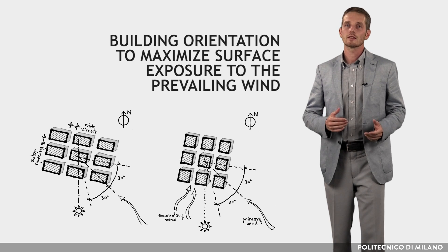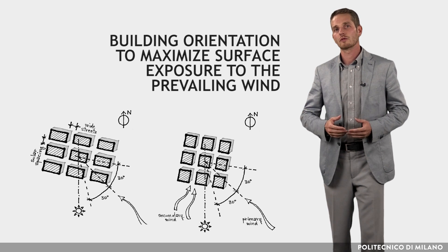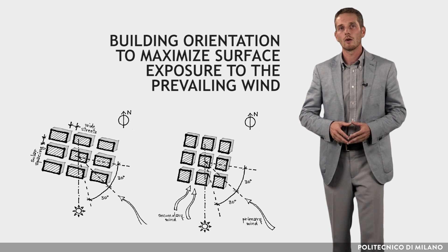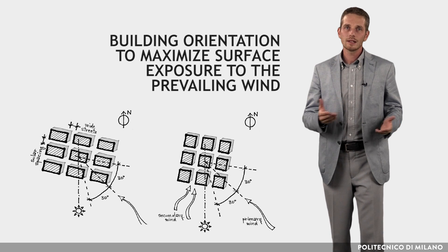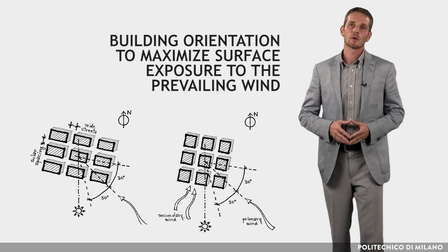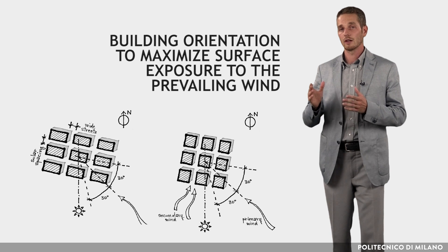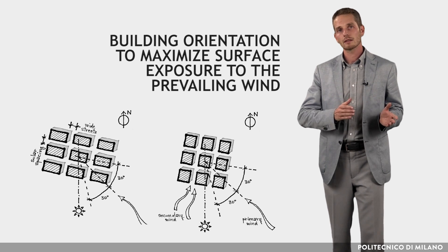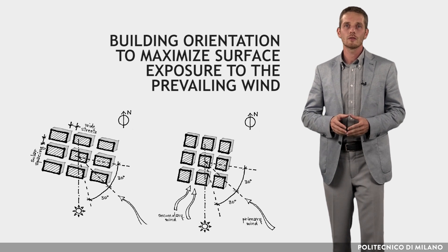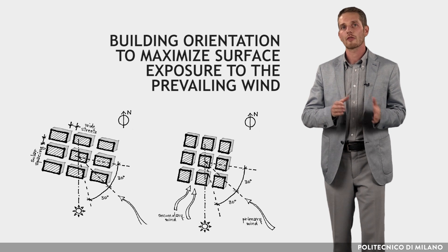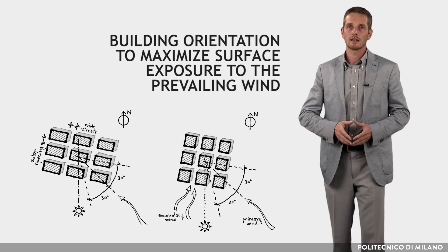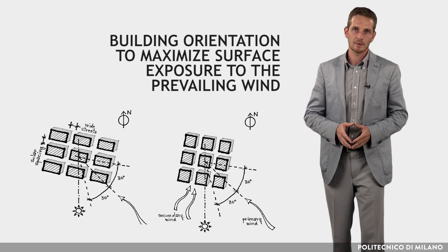Let's summarize some recommendations for best exploiting natural ventilation. The building should be oriented to maximize surface exposure to prevailing winds. However, a building does not necessarily need to be oriented perpendicular to the prevailing wind. It may be oriented to any convenient angle between 0 and 30 degrees without losing any beneficial aspects of the breeze.